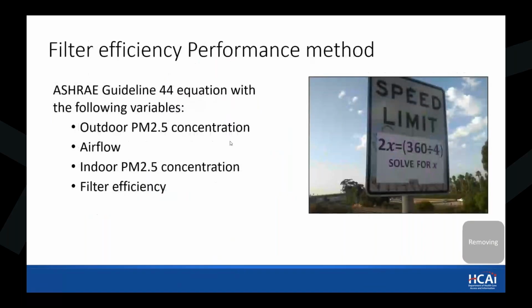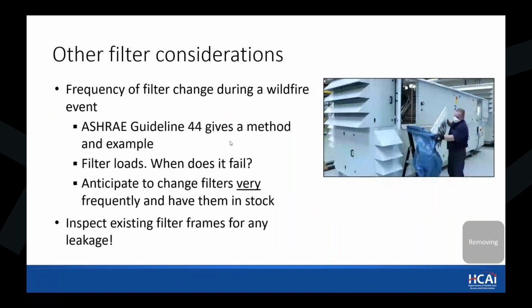Now, if you want to do the performance method, there is an equation. For the sake of time, I will not put it here, but there is an equation in Guideline 44 that you can use, based on the outdoor PM 2.5, the indoor PM 2.5, the airflow and the filter efficiency. You can fix three of those and come up with the fourth. Like if you have an outdoor PM 2.5 and you want to set a goal for the indoor and you want to know what filter efficiency will work, you can use that equation that's in Guideline 44. The most important is the frequency of the change.